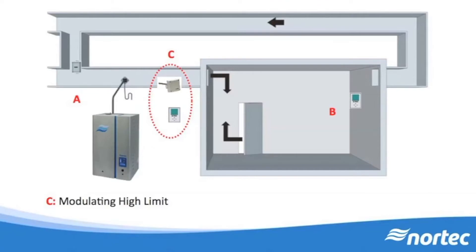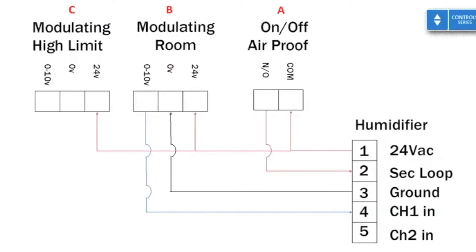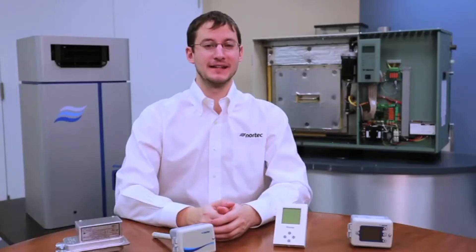Finally, the modulating high limit humidistat also wires to the humidifier's modulating loop. Note that the humidifier has two modulating channels to accommodate this exact scenario. We must wire power and ground to the humidistat. After this, we wire the modulating output, 0 to 10 volts DC, back to the humidifier and land it on channel 2 modulation, typically pin 5. Your wiring is now complete.